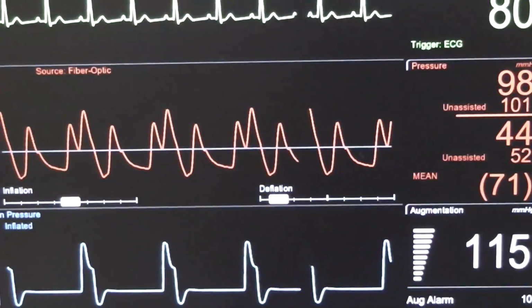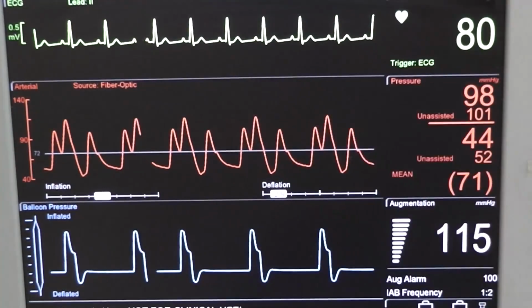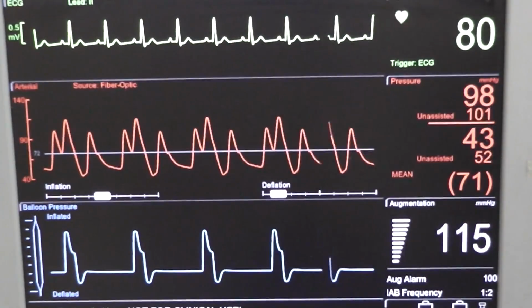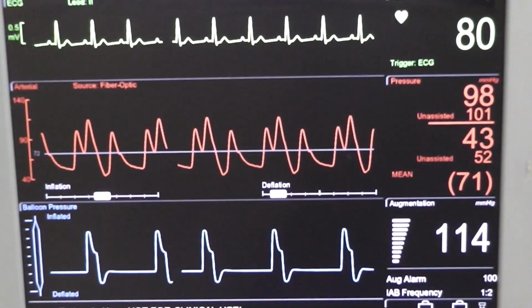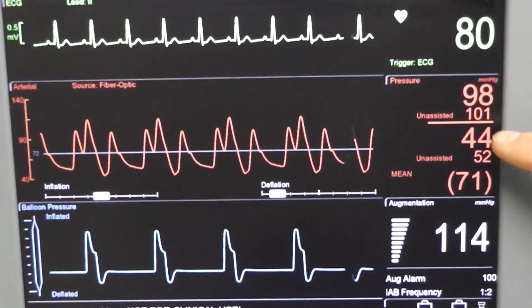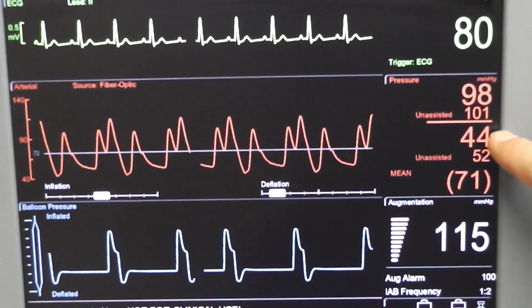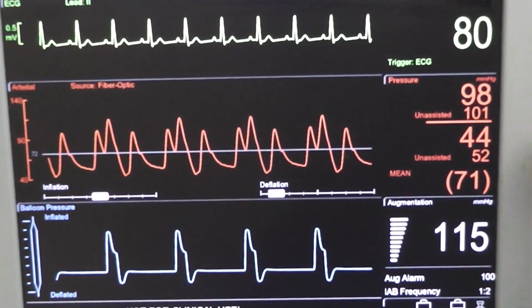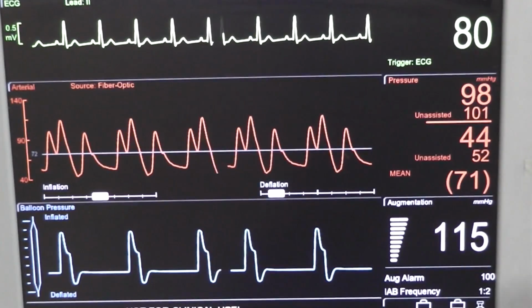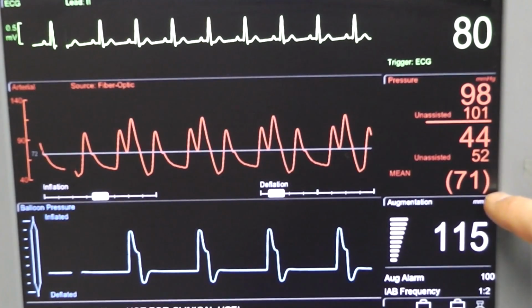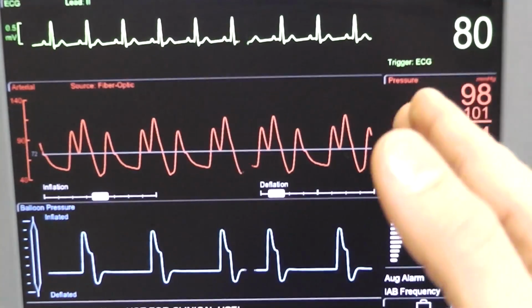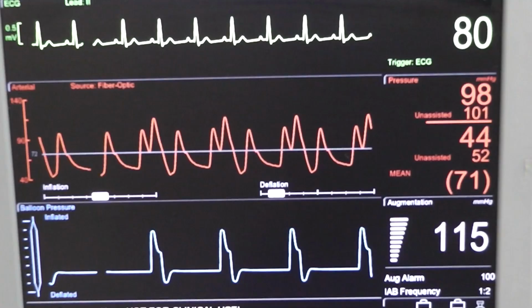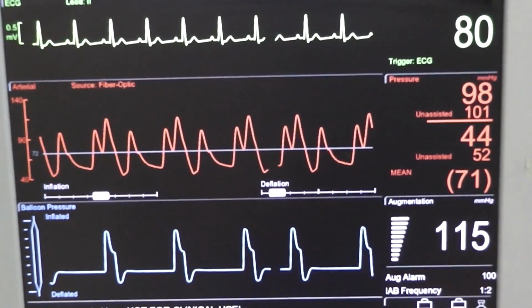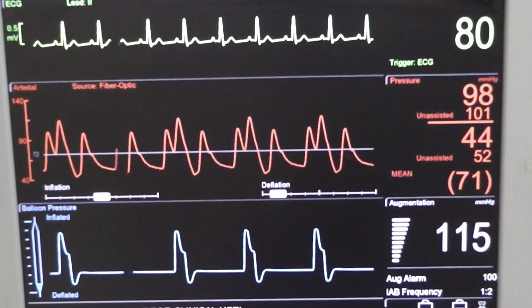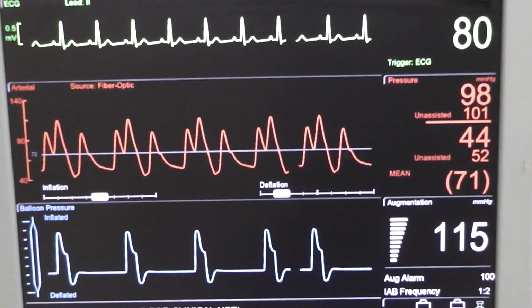So now that we have our inflation adjusted, it is time to adjust the deflation. And the way we do that is clearly our deflation is very early, and we want to start moving that progressively later until we reach the optimal point. And the way we see that is by looking at the diastolic assisted pressure here. We can see right now it's 44. And as we move that deflation later, we're going to start to see that diastolic pressure come down. However, once we get to a certain point, that pressure will actually start to come back up. And the optimal point that we're looking for is right when that diastolic pressure is at its lowest point for the assisted. So I'm going to start moving the deflation later.